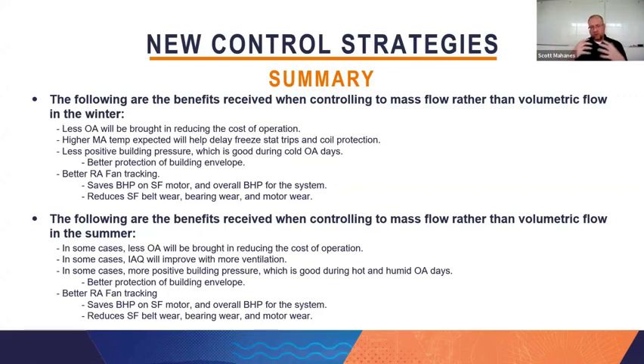Really, the benefits that occur when we do mass flow control versus volume kind of change between seasons. Basically, in the winter time, we achieve less operational costs because we're bringing in less outside air than we normally would. That also helps us with our mixed air temperature. We have a higher mixed air temperature when we're bringing in less OA of colder air. And so we have a little bit of savings there. We also delay the freeze trips or the coil protection that's necessary because we're bringing in a higher mixed air temp. We also usually get a less positive building pressure. And honestly, on colder days outside, we actually benefit from a neutral to slightly negative building. It's in the summertime when you really want a positive building. And so you get a lot of benefits in the wintertime.